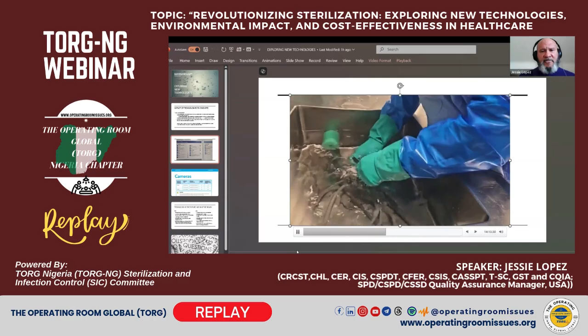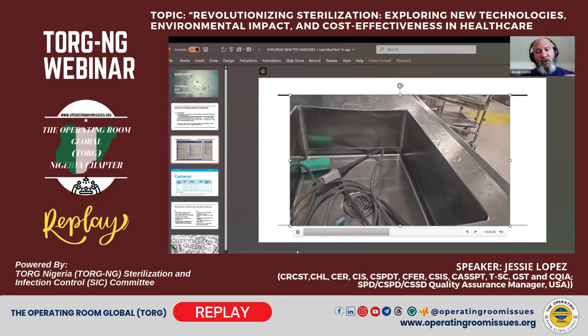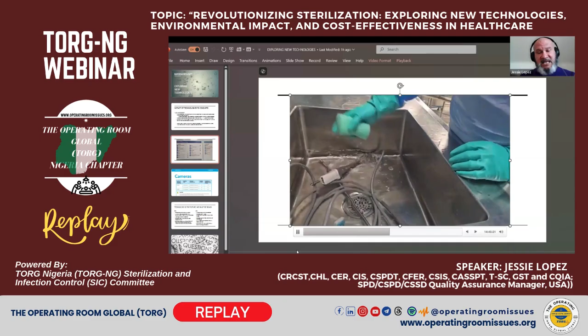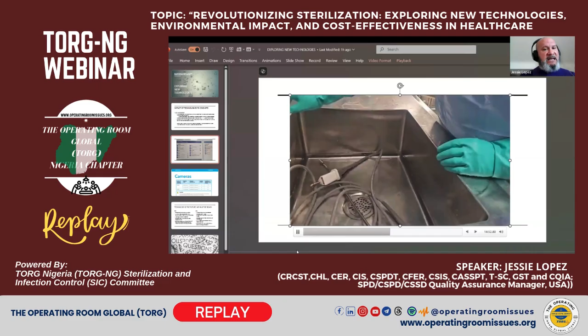Okay. So after this portion of the IFU, I will empty my sink, because this is utility water that I'm doing the initial rinse with. The final rinse, or the rinse prior to the ultrasonic cleaner, requires what we call critical water. Critical water is water that is free of minerals and microorganisms, because we do not want to redeposit any minerals or microorganisms back onto the device prior to going to the next step, even though the next step of the process is going to be an automated cleaning process.